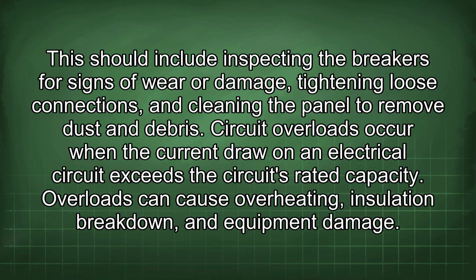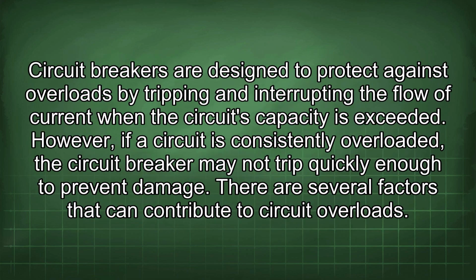Overloads can cause overheating, insulation breakdown, and equipment damage. Circuit breakers are designed to protect against overloads by tripping and interrupting the flow of current when the circuit's capacity is exceeded. However, if a circuit is consistently overloaded, the circuit breaker may not trip quickly enough to prevent damage.